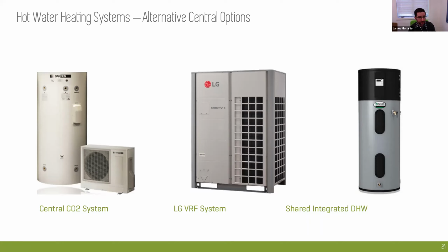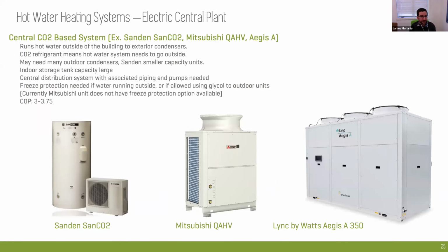The central CO2-based system, Sanden being the one on Ithaca, there are some other manufacturers. The middle one, we're seeing more and more now with the LG VRF system, and then just using off-the-shelf integrated hot water heaters, how those can work. So generally, some of the CO2-based systems, you have the Sanden system. That's more of a residential size, and you need a lot of them. As you saw on the Ithaca building, you just need a lot of outdoor condensers in order to handle the load. So you have a lot more hot water lines to run out the building, a lot more piping to install. So the cost of the Sanden, in particular on a big building, is the amount of units you need.